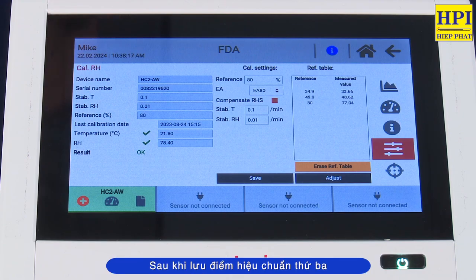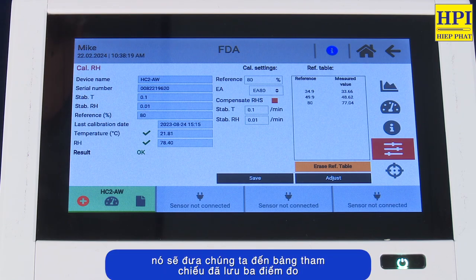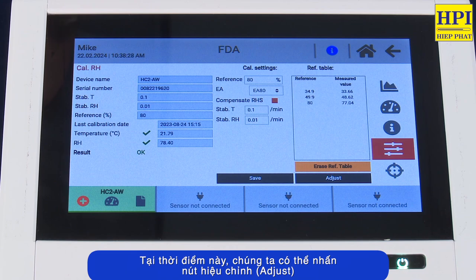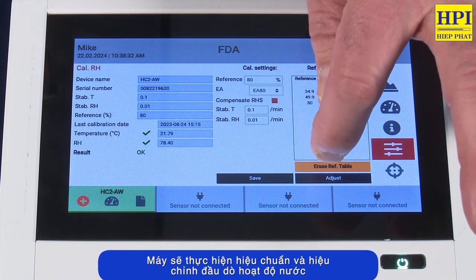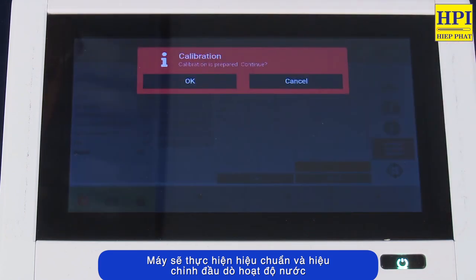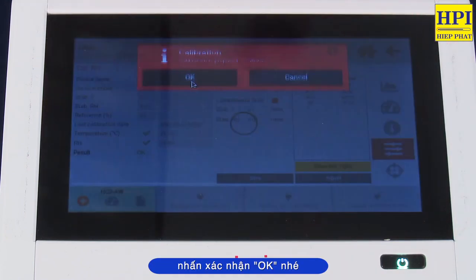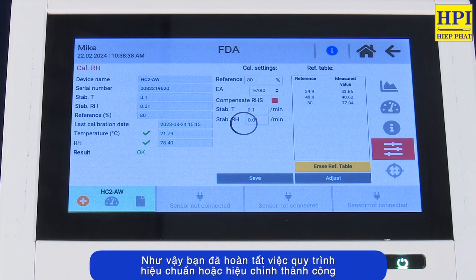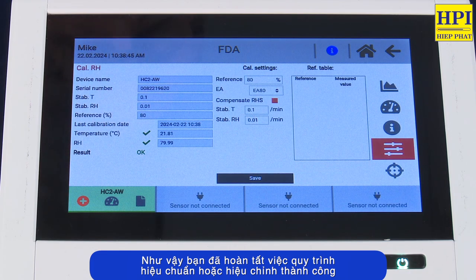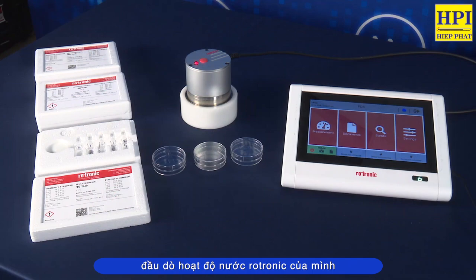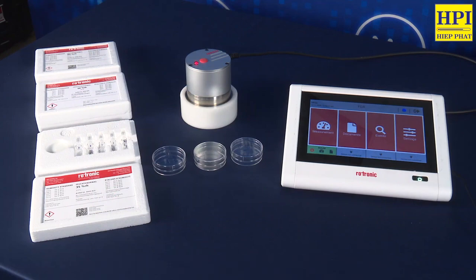So after saving that third calibration point, it brings us to the screen once again. We see now in the reference table that we have our 3 measurement points saved. It is at this time that we can go ahead and press the adjust button, which will then adjust and calibrate the humidity probe. We want to confirm OK. You have successfully adjusted or calibrated your Rotronic water activity probe. That completes the calibration procedure.